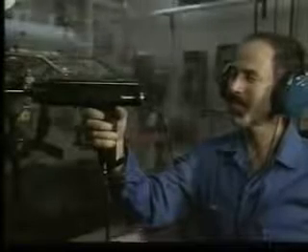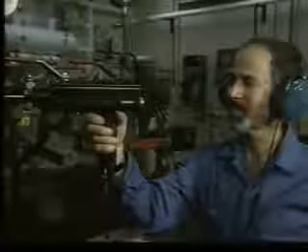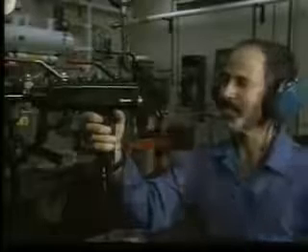When you become familiar with the sounds your traps make when they're functioning normally, it will be easy to recognize abnormalities in the system with the ultraprobe. We will now demonstrate the sound of the normal functioning of 5 major types of steam traps as heard with the ultraprobe. We will also demonstrate some common steam trap failures. This demonstration will show you what sounds to listen for. However, it will still be important for you to observe your own system and recognize how it operates under different load conditions and pressures.